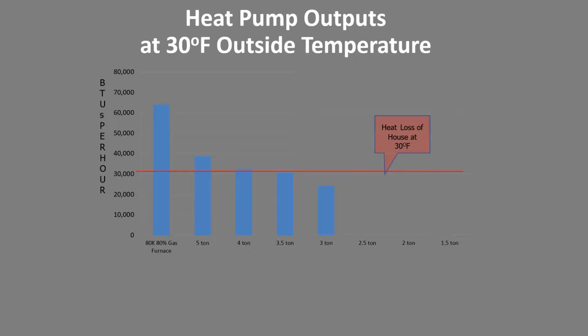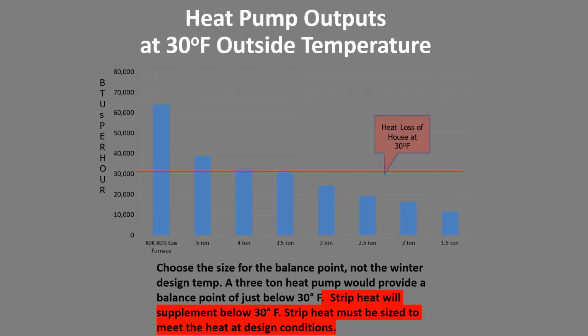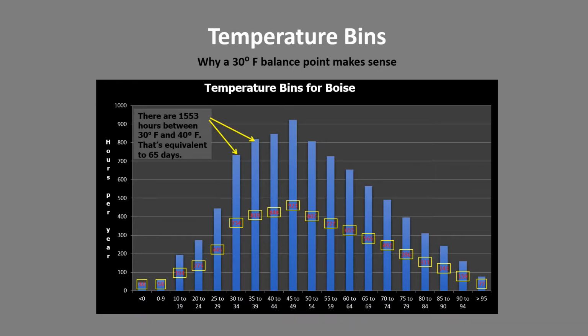3 ton, ooh, that auxiliary heat is really going to run. And by the time we get down to 2 and 2.5 ton systems, we can realize that we'll have lots of hours where the auxiliary heat is having to be used to keep the house warm. We hear a lot, why do we care so much about a balance point of 30? Why don't we make it 40 degrees? What this chart does here is it breaks the temperature in Boise, Idaho into 5-degree temperature bins. So this one right here is 40 to 45, this one is 45 to 49.